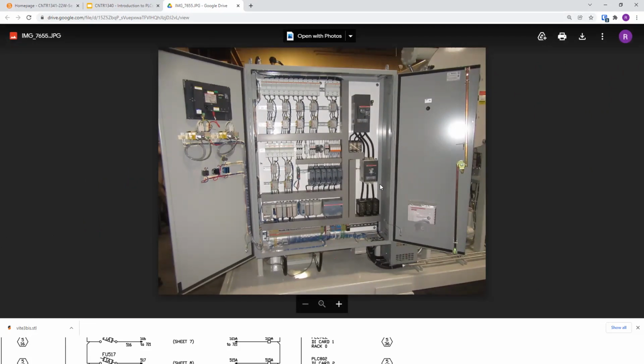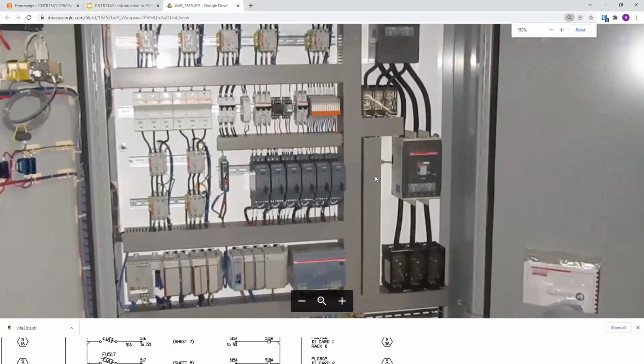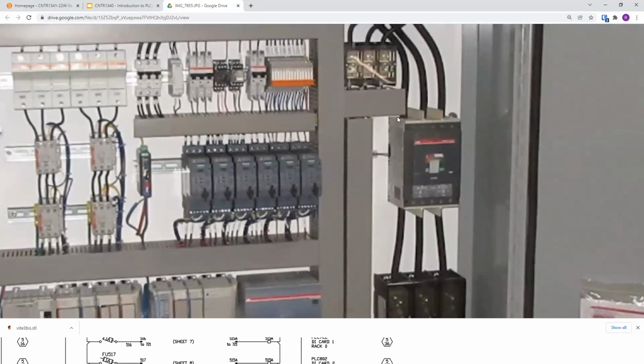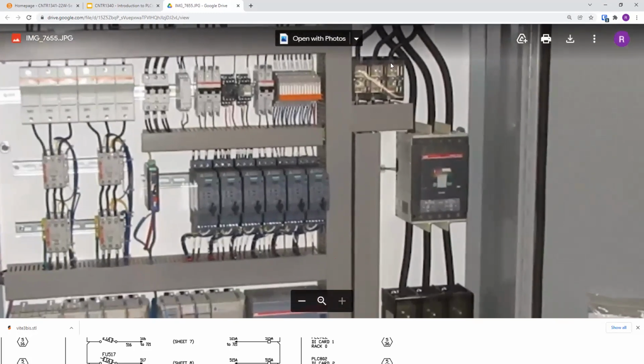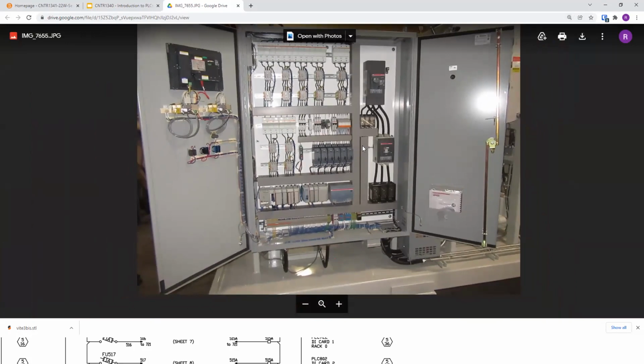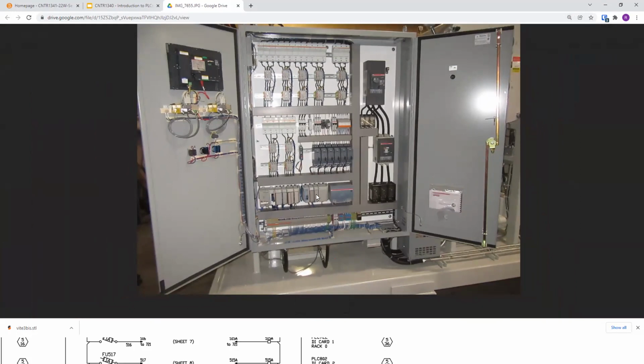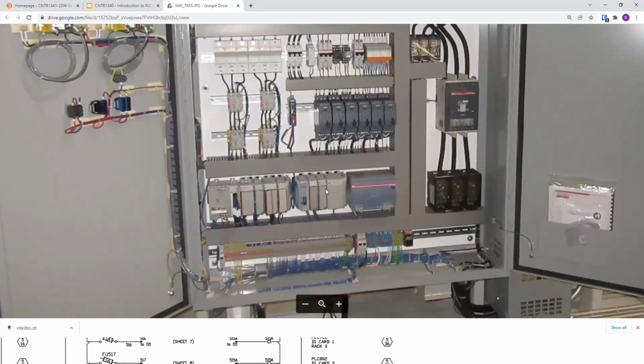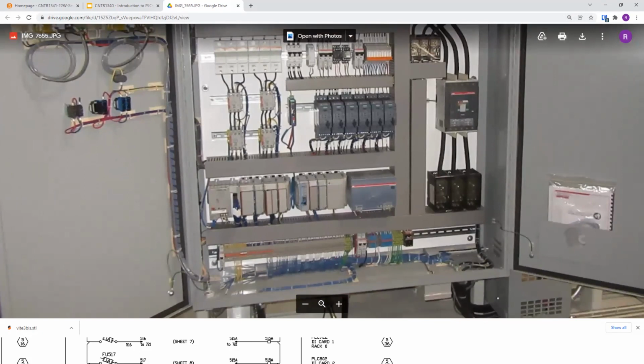So that looks like a high voltage breaker. And a separate heat input. I'm looking for a transformer. The transformers are down here. We've got, right, a CompactLogix PLC. All your IO, everybody see where I'm pointing here? Your IO looks like it's going to come in the bottom here. PLC panel or Modbus card potentially.